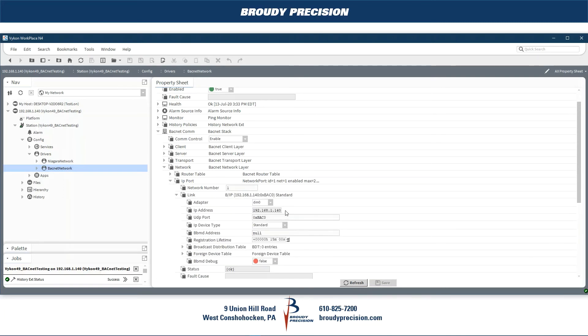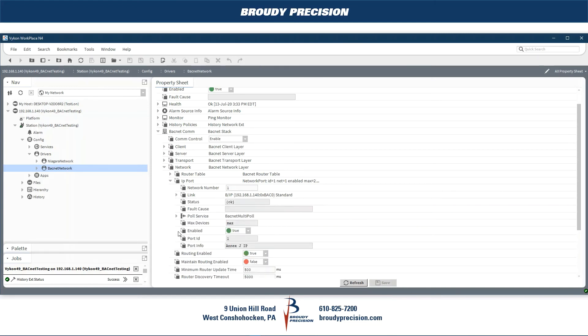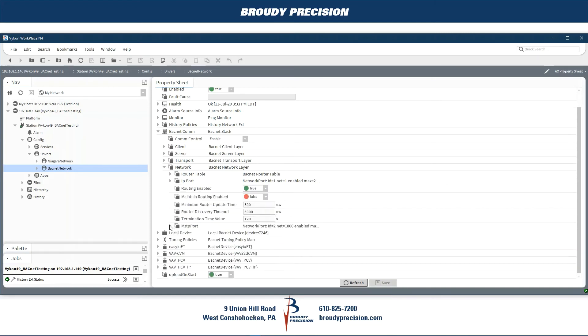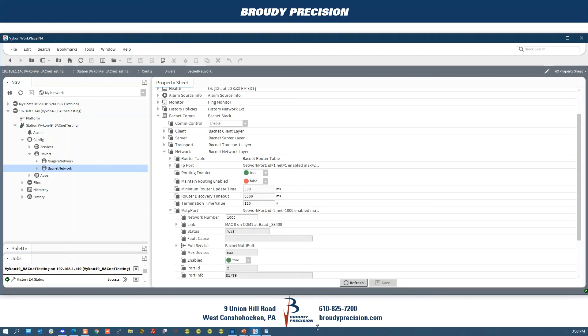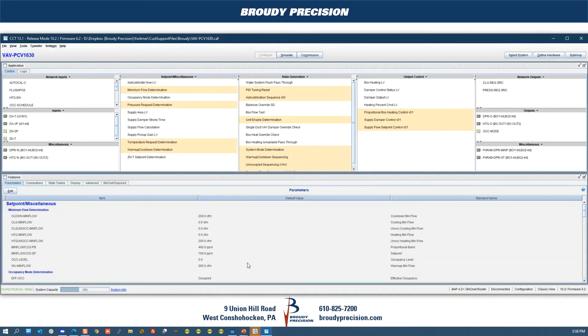Under the IP port link, you'll find the IP address being used for your BACnet connection. You'll also see the UDP port — BAC0 — which translates to 47808. And if we look at our MSTP port, the network number is 1000. So those are the values we'll now enter into CCT before doing a download.